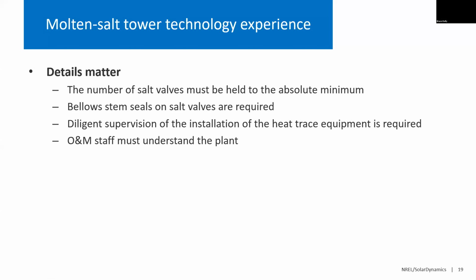If they leak, they'll often wind up causing heat trace failures, due to the heat trace cables becoming exposed to salt and then winding up with corrosion of the heat trace cables. And really, the best way to control that is to provide a bellows stem seal on all salt valves. There's a lot of objection to that because they're expensive and finicky, in the sense that it's easy to break them. But at the end of the day, if you can prevent a salt leak, even with an expensive component like a bellows, it pays rich rewards later on in the operation of the plant.